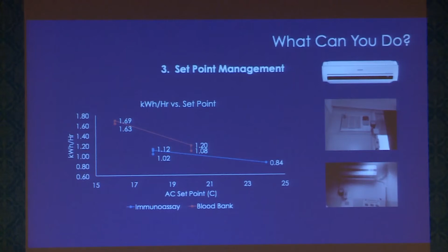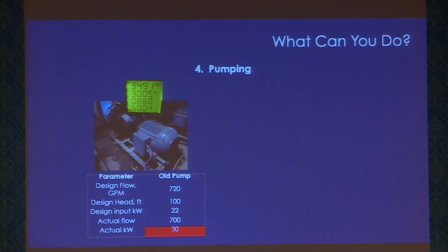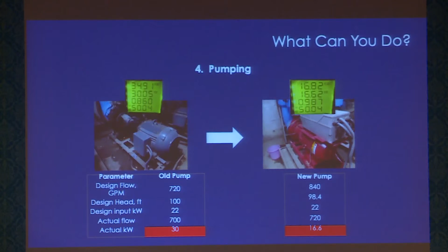And in pumping. So this is an older pump which is in one of our facilities before Smart Joules went there. It was having a head of 100 feet and a flow of 720 GPM, and it is consuming 30 kilowatt per hour. And now see, we have retrofitted the older pumps with a new pump, and we are not compromising on the head, and the flow is 120 GPM extra. But see, the energy consumption is nearly half. And one more thing is that we can change the flow according to our wish based on the ambient temperature of the atmosphere, and at the same time the cooling demand of the building. So we can again reduce this 16.6 to maybe 10.6 or even to 7.6 based on the cooling demand that the facility requires.